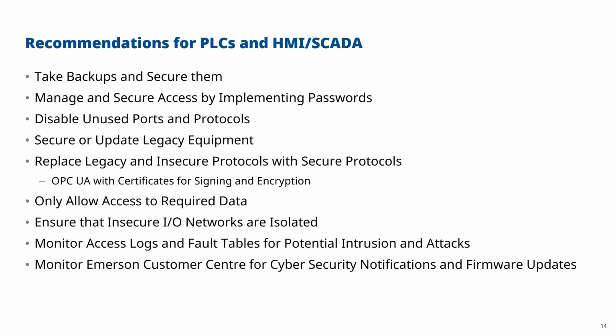If there are legacy and insecure protocols, they can be upgraded or replaced with secure protocols. This is where OPC-UA with certificates for signing and encryption comes in. Other protocols could include MQTT, which can be secured. And if you can't secure the protocol itself, you could consider wrapping it inside a virtual private network or VPN to make sure no one can interfere with or read that data.